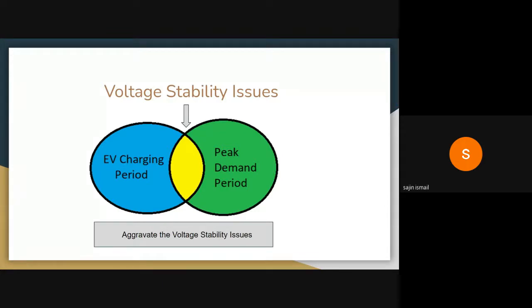At that time, an additional load of enormous nature comes in. What can the grid do? It can simply sit and watch if it's not prepared for it. So this is what happens when the EV charging period coincides with the peak demand period. I'm showing it as a small yellow part here, just a small joining. As this area increases, the aggravation of voltage stability will be very high, because the peak demand is already very difficult to harness.